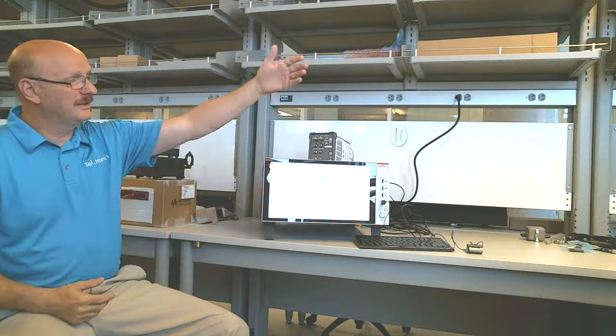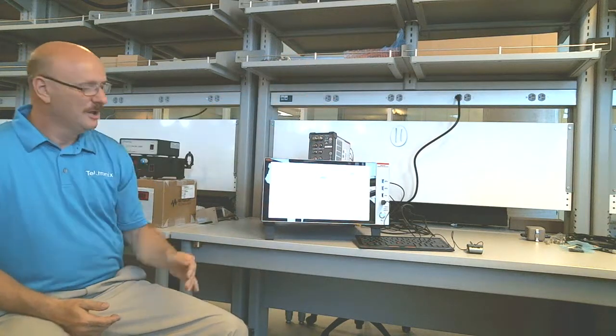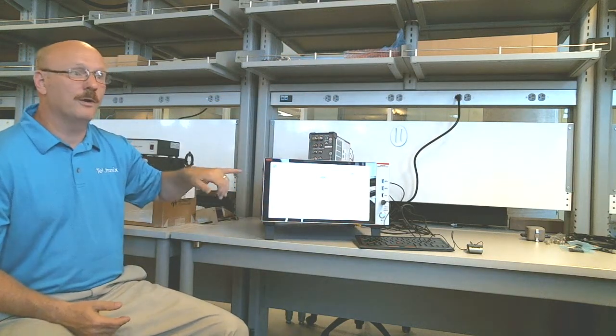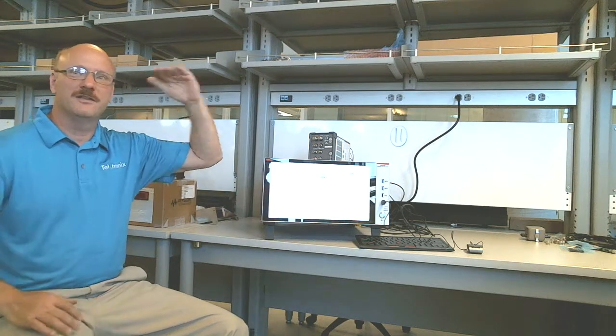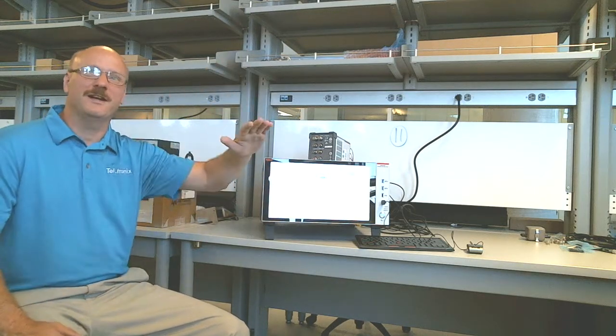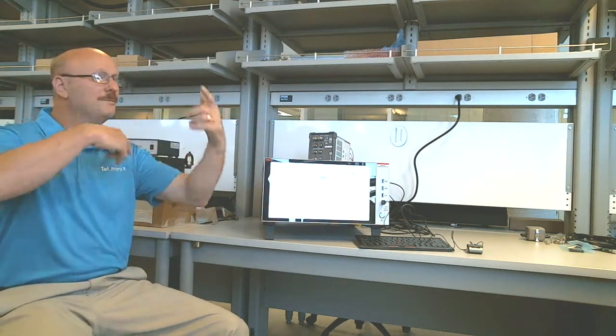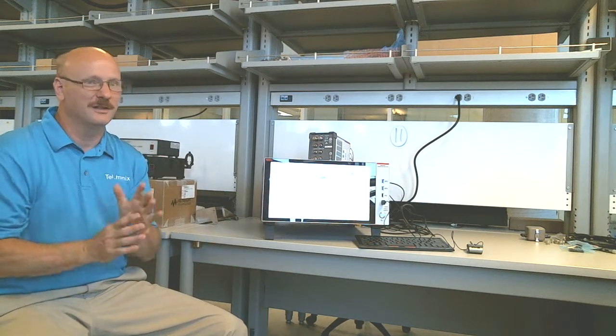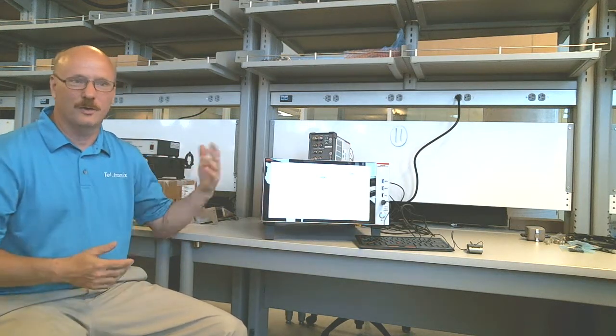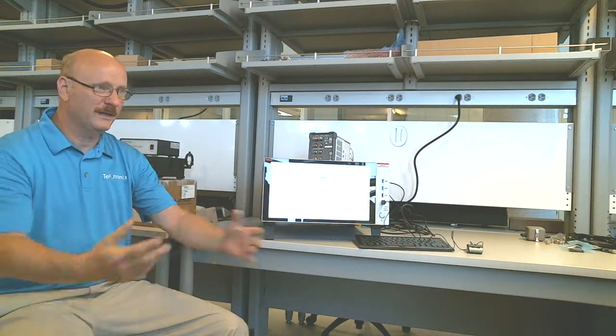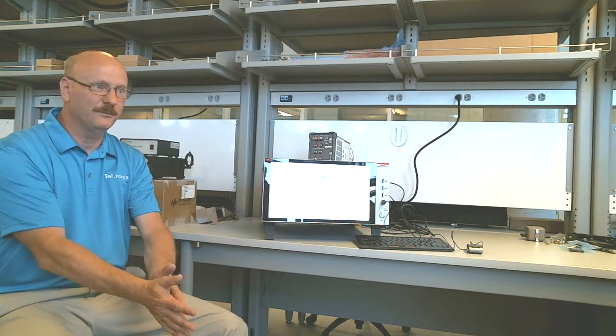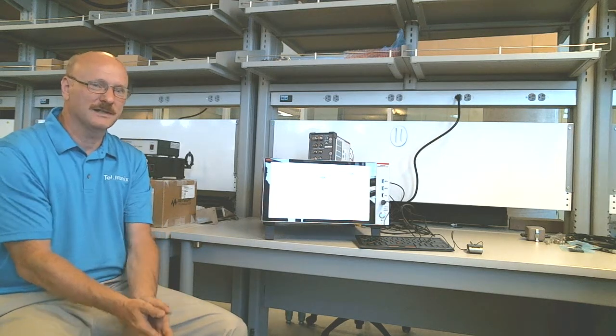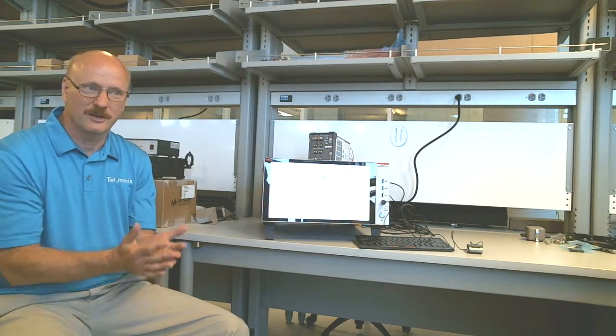That's how you'll do things like with your probe station. You'll add tests in here to move your prober, for instance. You'll run a test, then index the prober, run a test, index the prober. You can put loops in and do all kinds of really cool logic with the code and your external equipment. You can control anything you want externally, anything that's GPIB. That's how it works, it uses GPIB to talk to the outside world.